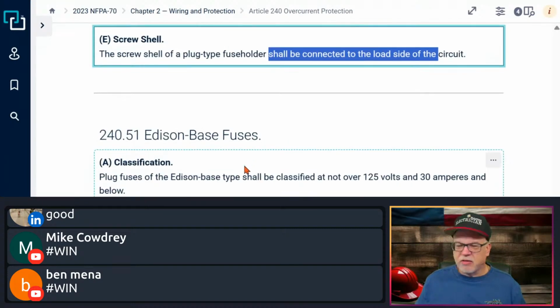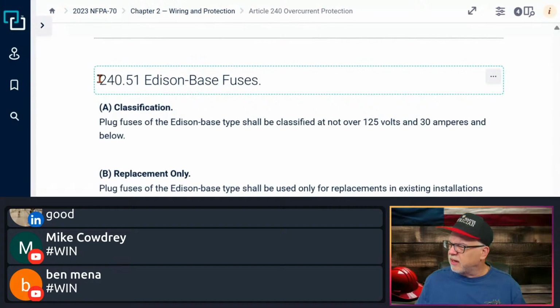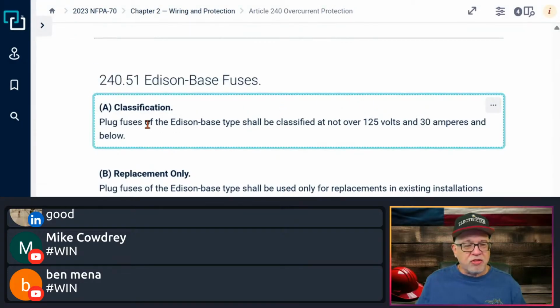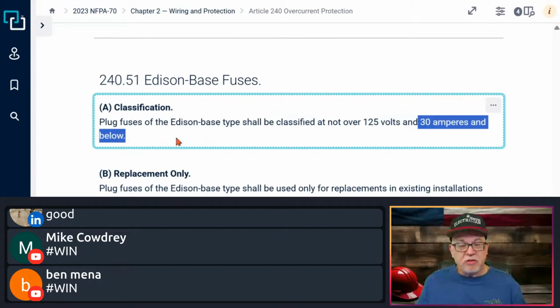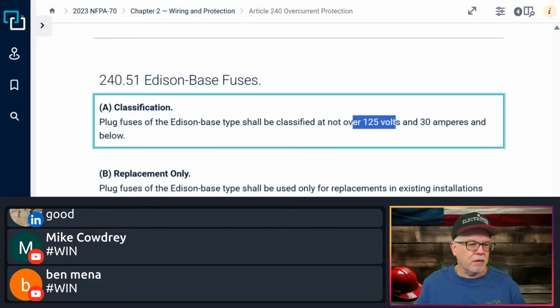Also, by the way, this is 240.51 for Edison-base fuses. Okay. I do see these on exams. So the only reason I stopped here is because I do see this classification. Plug fuses of an Edison-base type shall be classified as not over 125 volts and 30 amperes and below. So again, sometimes low-hanging fruit on exams, when it asks you something about an Edison-base fuse, or it might ask you for the maximum voltage rating on a 20 amp Edison base fuse. Okay, and you say, okay, well, what is it? Well, there it is right there. Okay.